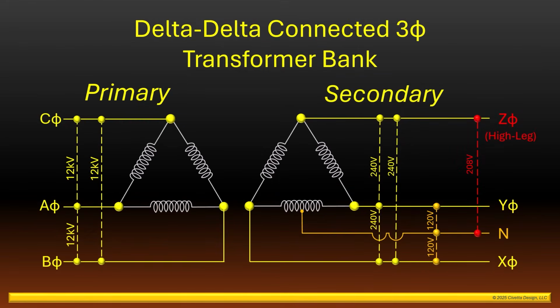So this delta-delta connected three-phase transformer bank is connected in a delta configuration on the primary side to the A phase, B phase, and C phase primary conductors. The voltage between each of the primary conductors is 12,000 volts. The secondary side is also connected in a delta configuration, capable of providing single phase 120 volts, 240 volts, three-phase 240 volts, and the anomalous single-phase 208 volts.